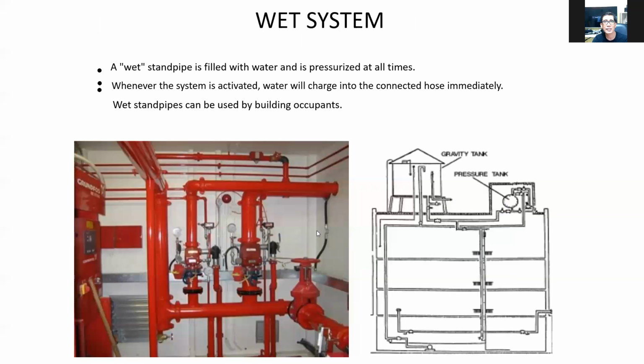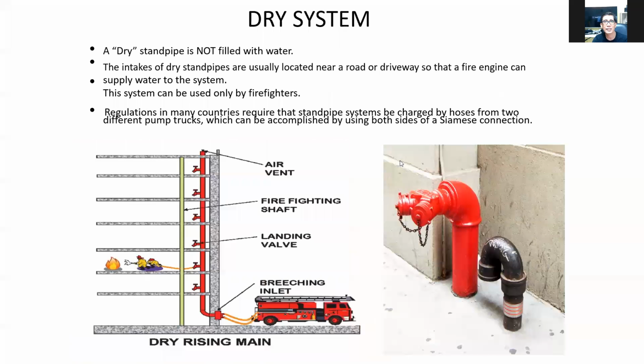So the wet type, as you can see, no, this is the wet type. A wet standpipe is filled with water and pressurized all the time. So it means that the fire suppression system is always filled with water. Whenever the system is activated, water will charge into the connecting hose immediately. A wet standpipe can be used by building occupants. So this is usually in buildings where there is water inside the fire suppression system. The dry type standpipe is not filled with water. There is no water inside the dry type. So the system can only be used by firefighters, no? And there is this Siamese twin, where the fire truck will connect the hose to the Siamese twin, and then there will be water inside the fire suppression system. Okay.